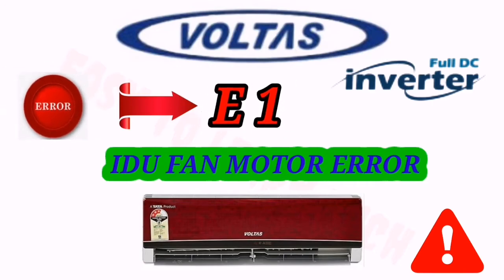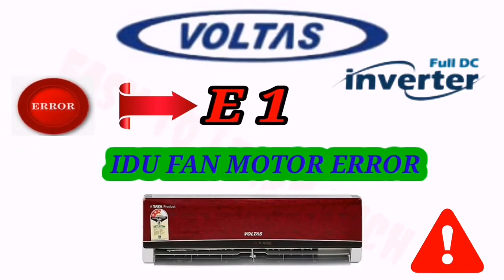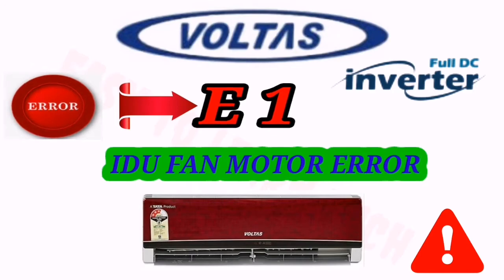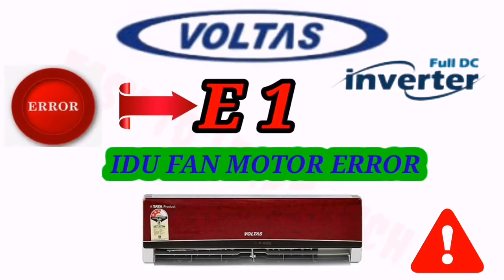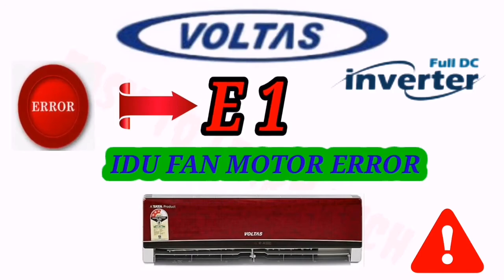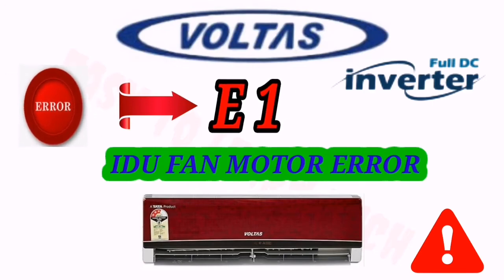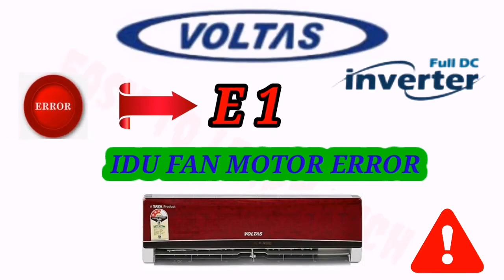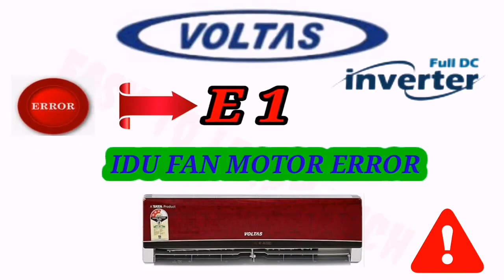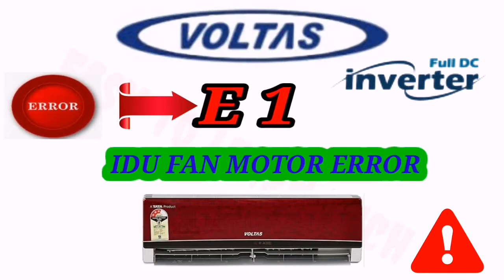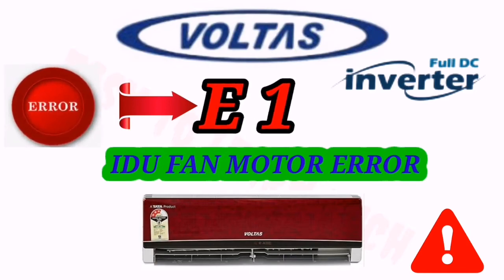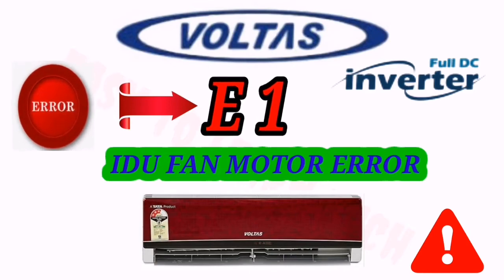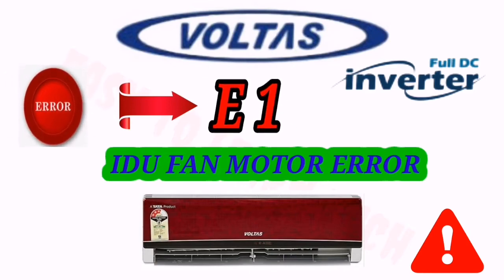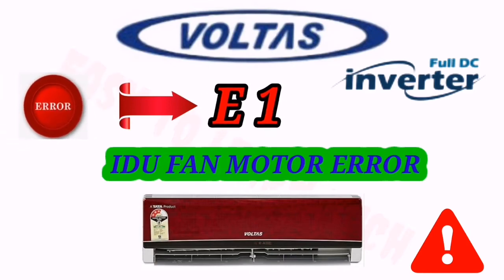Then you have to check the airflow, whether there is any obstruction or not. You have to make the airflow smooth. Sometimes when the capacitor is weak, it also doesn't work, so you have to check the capacitor also. You also have to check the indoor PCB: the output supply coming from the indoor PCB should be DC 5V. If it is not giving DC 5V, it means our indoor PCB is faulty. You need to change the indoor PCB.